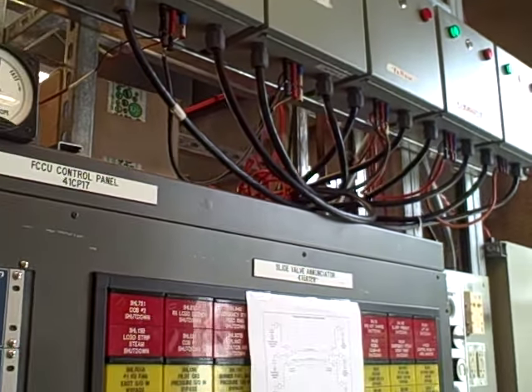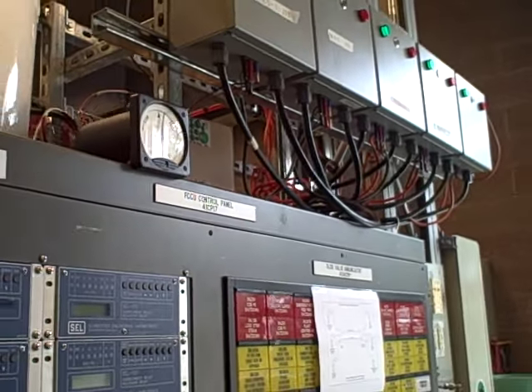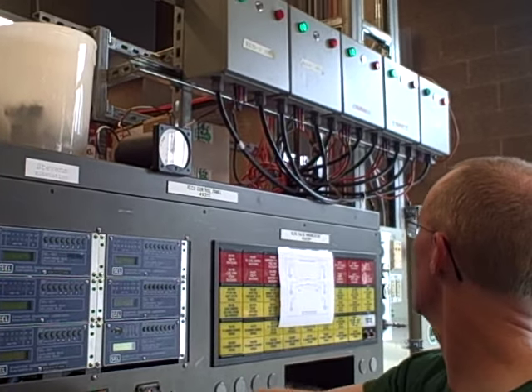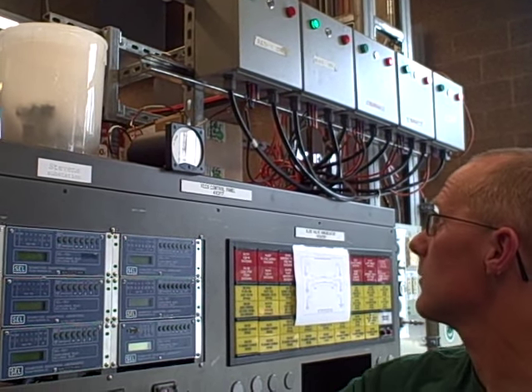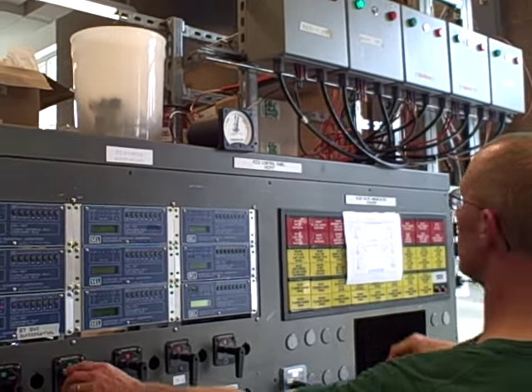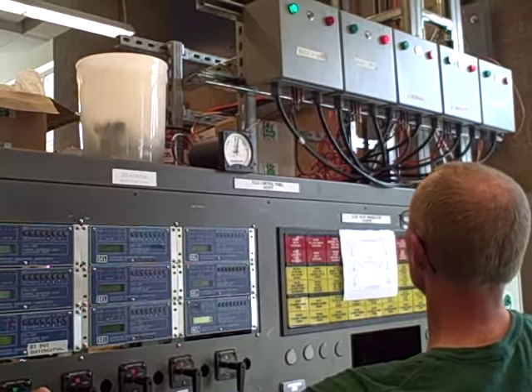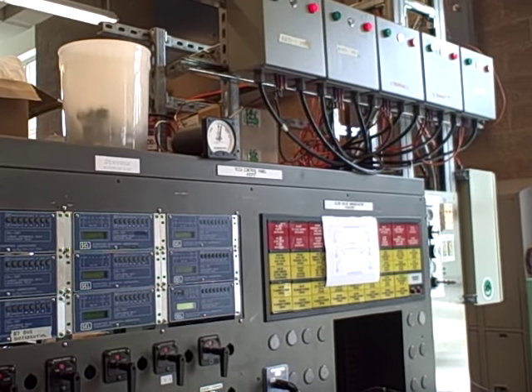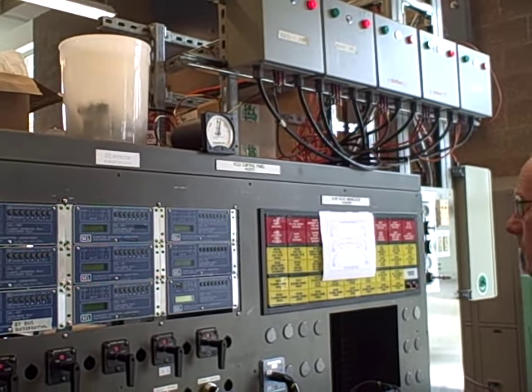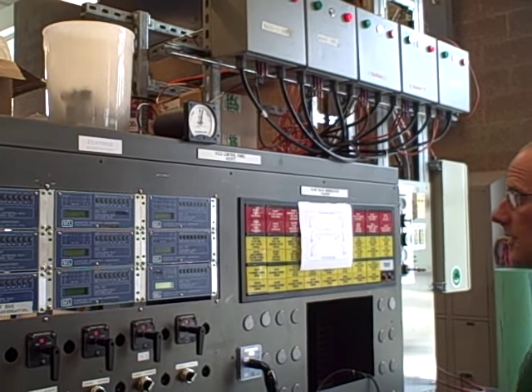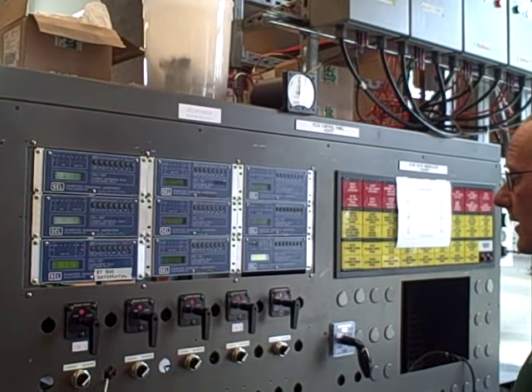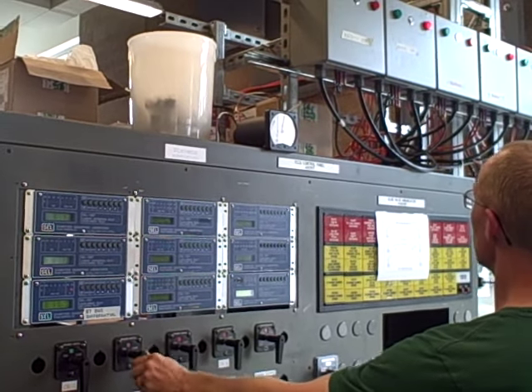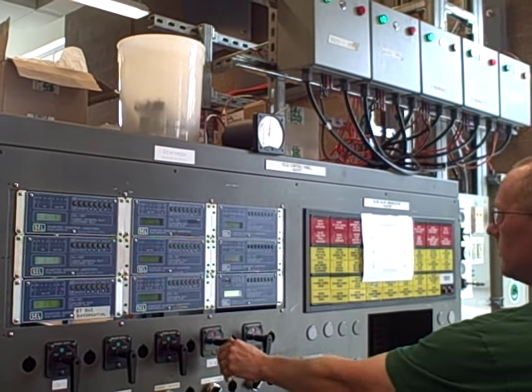We can demonstrate how the breakers work. I've got my five handles down here. I can close each breaker. And as we look up to the circuit breakers up there, you can see the lights change color, changing states. Now all five breakers are closed. Currently, none of my generators are running so it really doesn't matter what I do with the breakers in this state. I don't have to worry about sequence or anything else. I just want to demonstrate how we can trip and close each one.